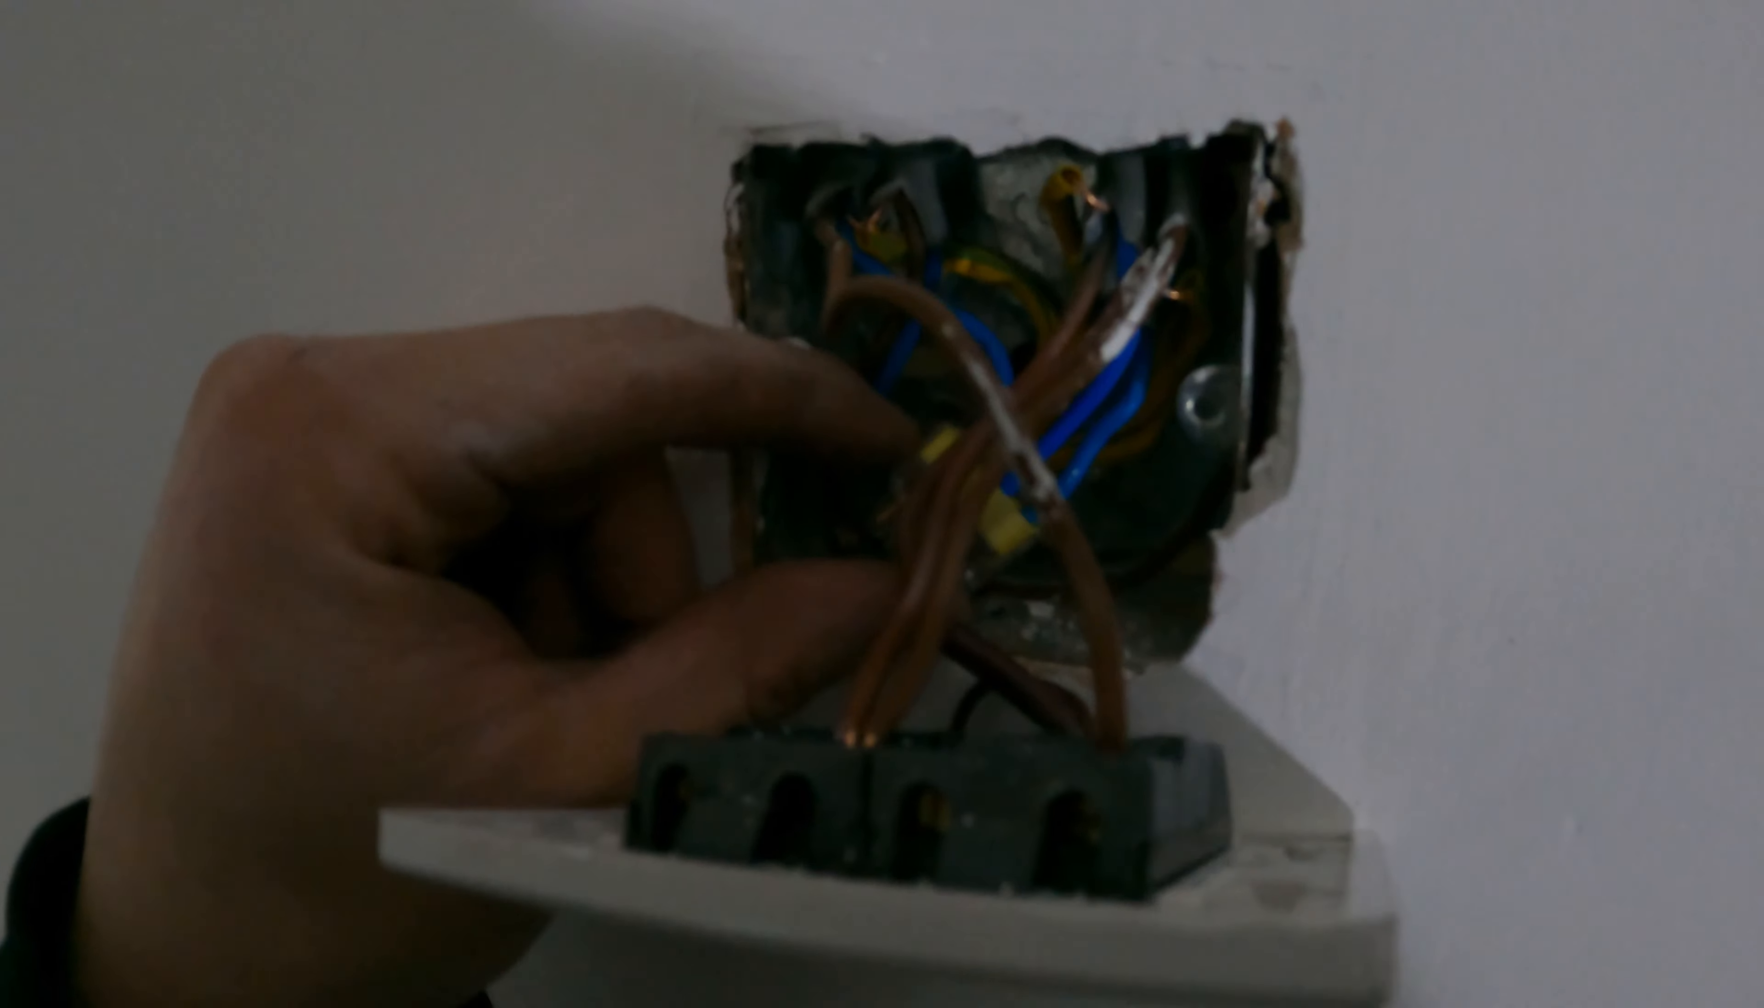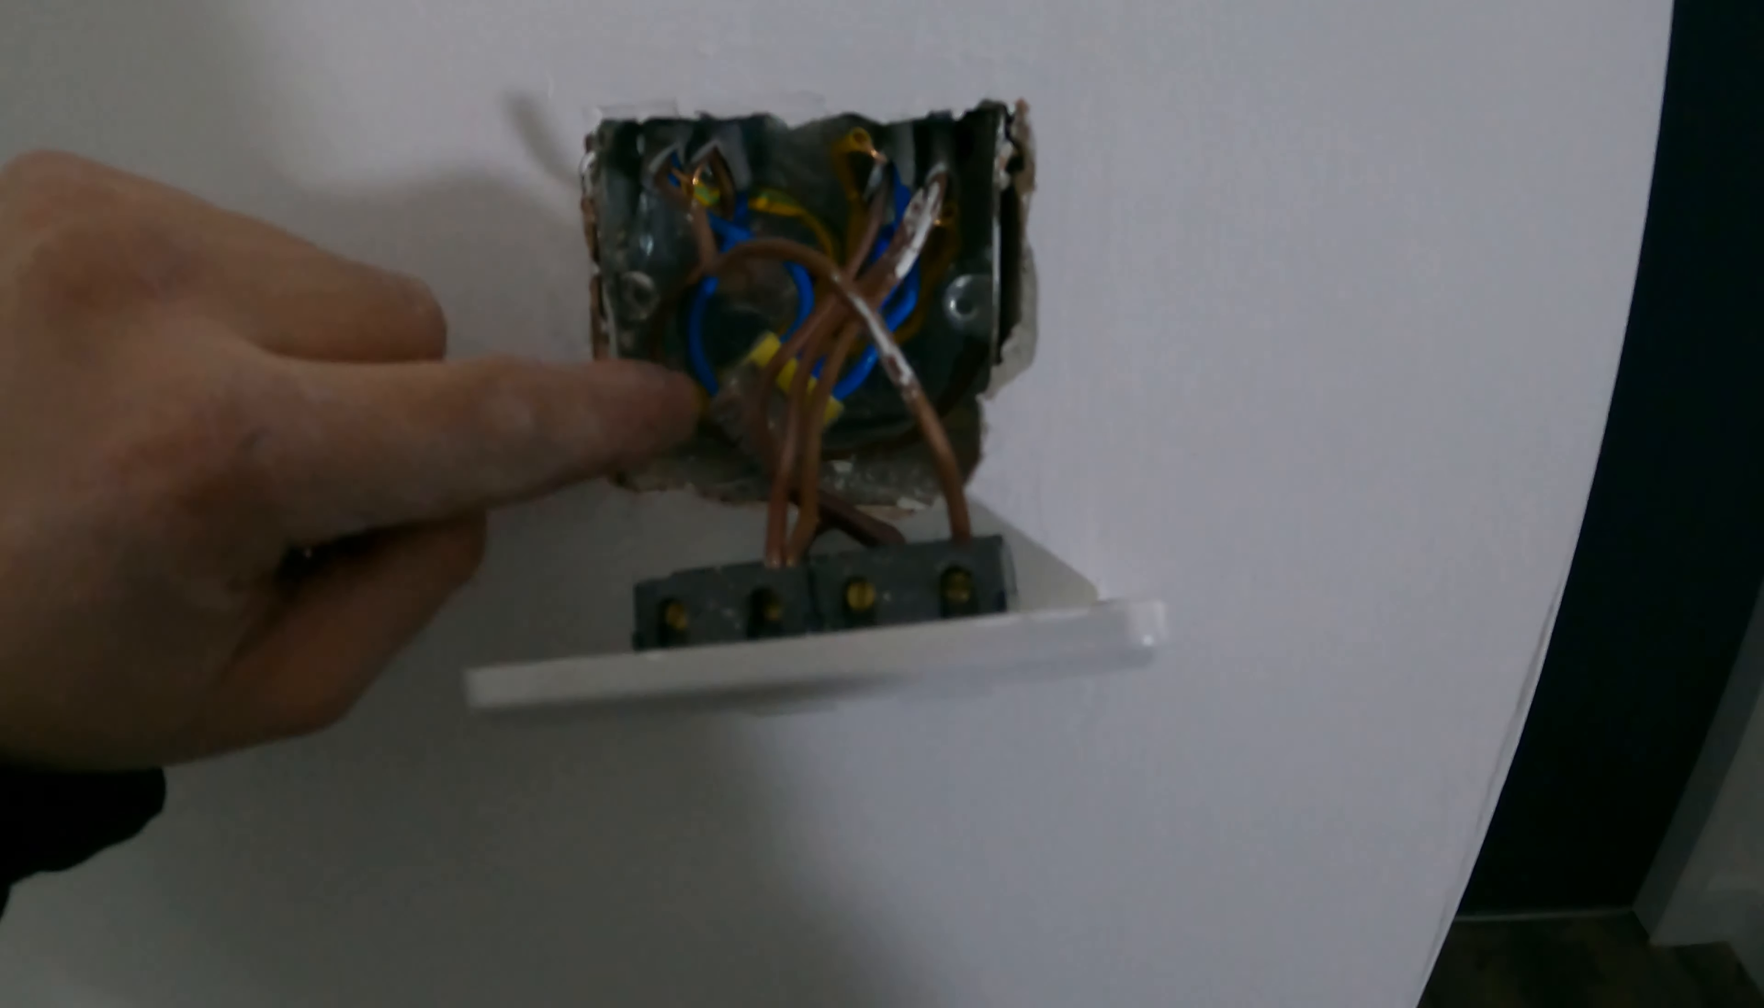His cables, when I've seen above the ceiling in the other flats, he's clipped them all along the joists and whatever. He's even used ideal connectors—that's because Screwfix was giving them away free with cable. Definitely why. So yeah, what we've got here, we've got our feed coming into the common at the bottom and he's linked that over. He's also taped it up, so I don't want to look underneath that.